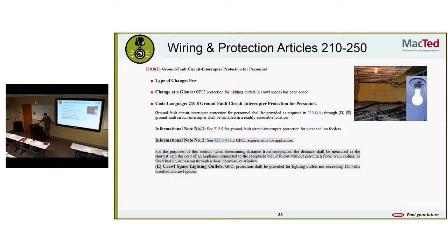New GFI protection for lighting outlets in crawl spaces has been added. So this looks like this is probably for dwelling units. So now GFI protection shall be provided for lighting outlets not exceeding 120 volts, so even your lights. So if you have a light down in a crawl space, it needs to be protected by a GFI. So if it gets contact with earth or you get caught between changing the light bulb and the ground, you don't get shocked and your wife find you down there or something. Pretty much if you're replacing outlets, you should probably put a GFI in there. That's what it sounds like to me.